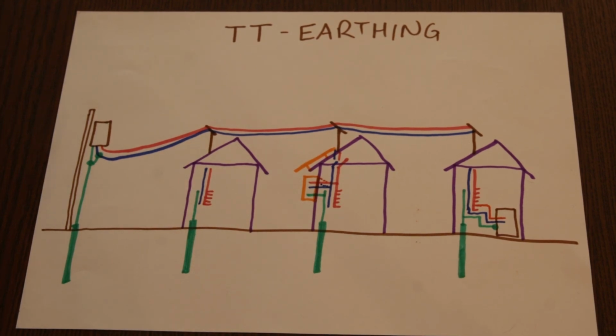So what's a TT earthing system? The TT earthing system is the second most common earthing system used globally. It is specifically used in rural areas. This is where the consumers are situated furthest away from the transformer. And what's the importance? If somebody installs a solar system on his house and wants to still interact with the grid, what does he have to take care of? What needs to be considered in that case? What is the TT earthing system and why is it so tricky when it comes to installing solar systems, especially ones which do interact with the grid?